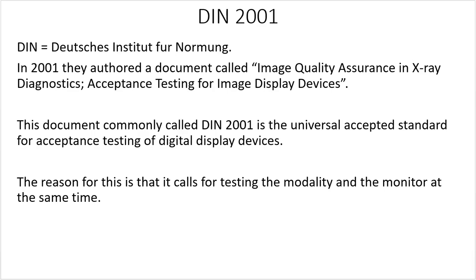DIN 2001 — DIN stands for Deutsche Institut für Normung. In 2001 they authored a document called "Image Quality Assurance in X-Ray Diagnostics: Acceptance Testing for Image Display Devices." This document is commonly called DIN 2001 and it is the universally accepted standard for acceptance testing of digital display devices. The reason for this is that it calls for testing the modality and the monitor at the same time.